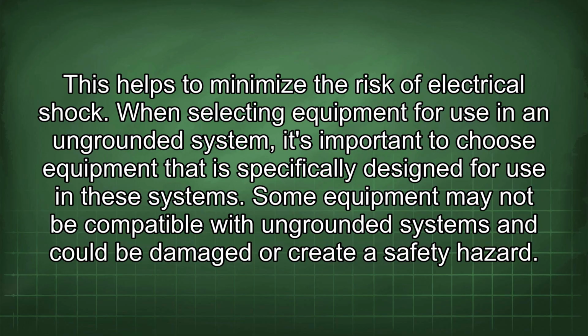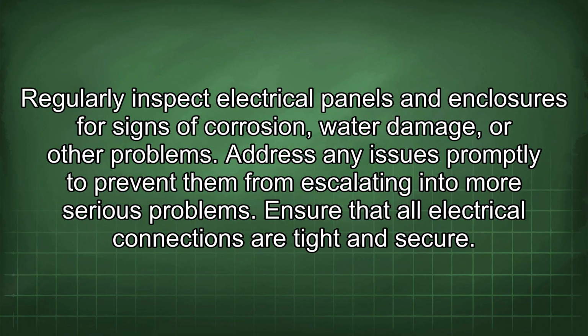When selecting equipment for use in an ungrounded system, it's important to choose equipment that is specifically designed for use in these systems. Some equipment may not be compatible with ungrounded systems and could be damaged or create a safety hazard. Regularly inspect electrical panels and enclosures for signs of corrosion, water damage, or other problems. Address any issues promptly to prevent them from escalating into more serious problems.